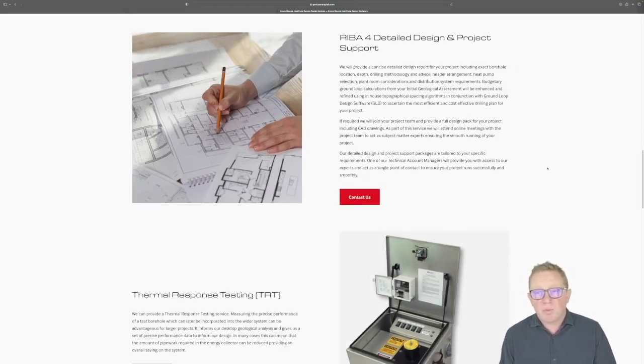Further on from there, we'll provide a concise, detailed design report - exact borehole locations, depth, the drilling methodology we'd advise, any header arrangements, heat pump selection, plant room considerations, distribution system requirements, etc. We can also provide full design packs at this stage. So if you need something in addition to the ground loop side of things, the ground collector, we can do CAD drawings in 2D, or even 3D plant room modeling if that's what you require.